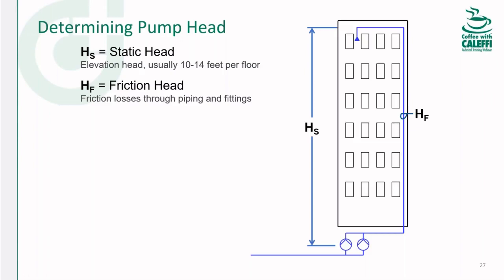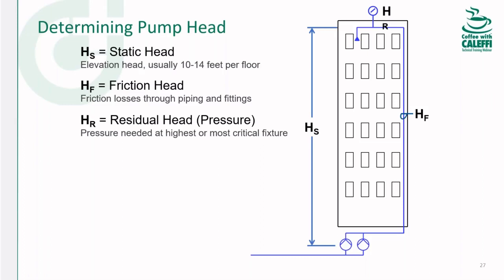You know, for closed loop systems, think boilers and chiller loops. Friction head is the major component of your total dynamic head, but for pressure boosting, it should be minimal, provided that your risers and piping are all sized correctly. Next, we've got the residual head. So this is the pressure that you want at the highest point, so typically 20 to 40 PSI.